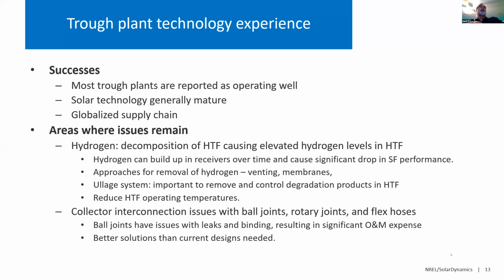The second area where there was significant concern is the collector interconnection: ball joint assemblies, flex hoses, rotary joints. Those have been an area with fairly high failure issues. Most pressing are either leaks or binding of ball joints, and those cause problems. They have been a fairly significant O&M expense at many plants. Although the current designs can work, better solutions are needed. Designers are paying more attention to this, and I think coming up with some better designs these days. Next slide, Mark.